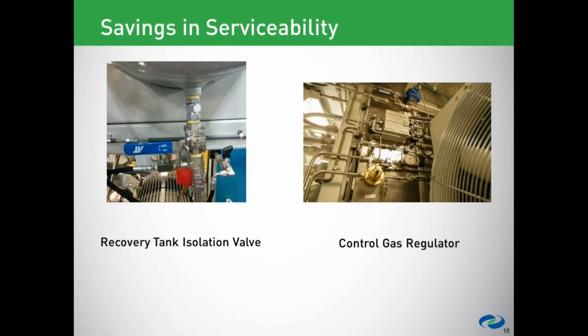to the relief valve. This allows that gas that's in that tank to be saved when servicing the relief valve. That was the line drained, the relief valve disconnected, recertified, reinstalled without having to drain all of that gas, which goes into the atmosphere and it's basically just blowing money into the air.